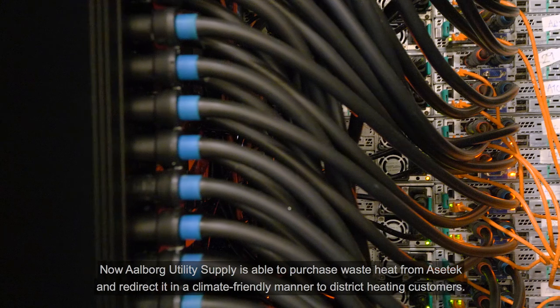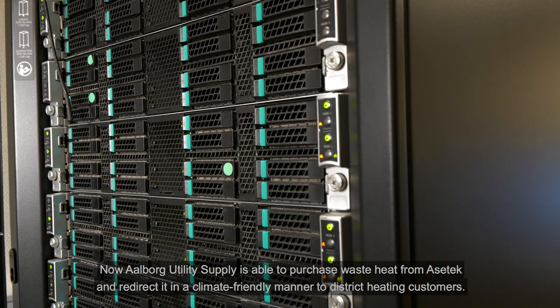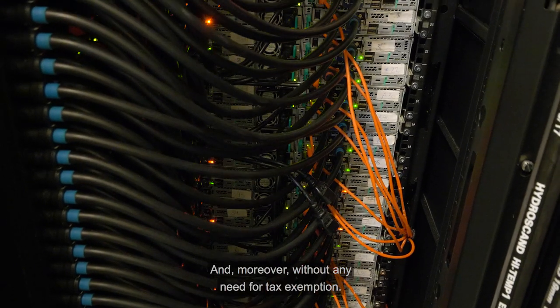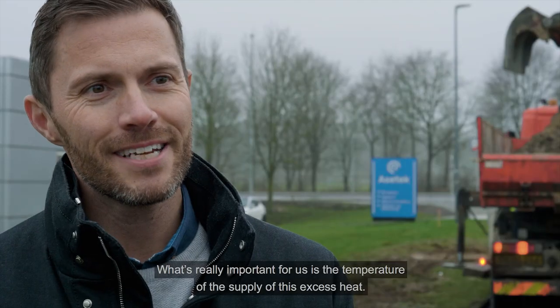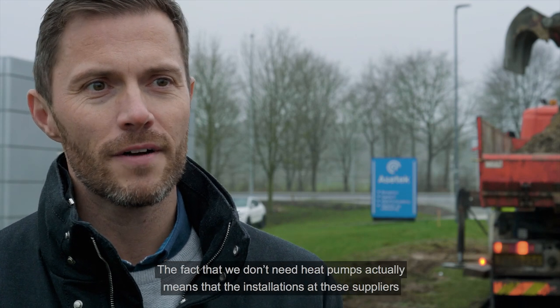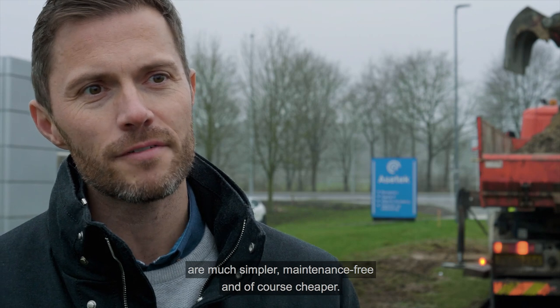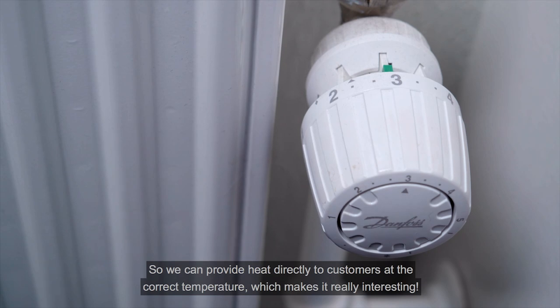Now, Aalborg utility supply is able to purchase waste heat from Asetek and redirect it in a climate-friendly manner to district heating customers. And, moreover, without any need for tax exemption. What's really important for us is the temperature on the delivery of this heat. We don't need heat pumps. It makes the installation simpler, more reliable, and we can get heat at the right temperature to the customers.